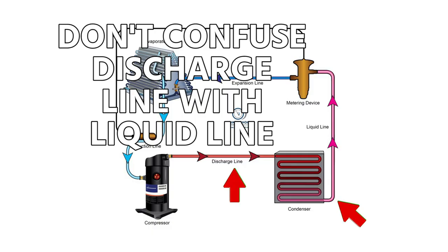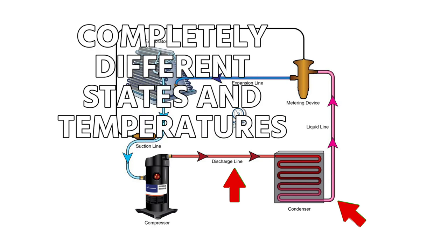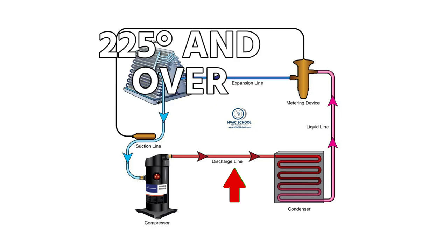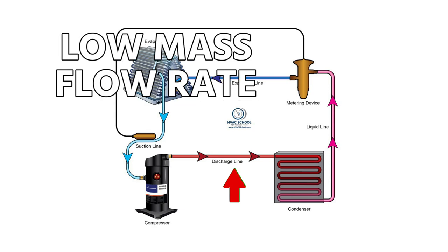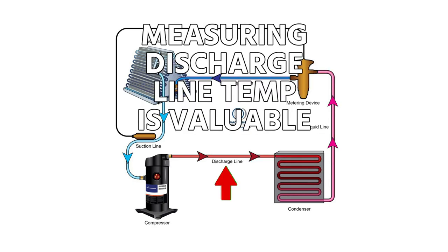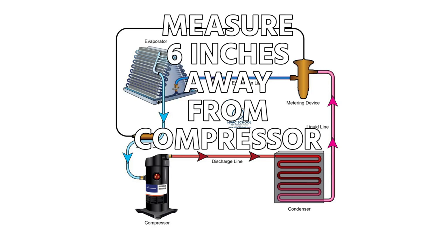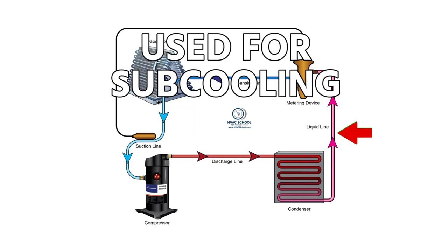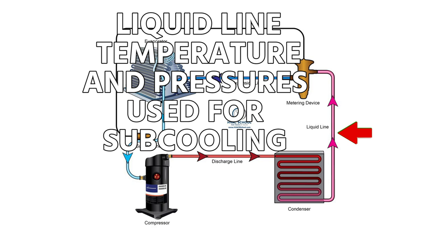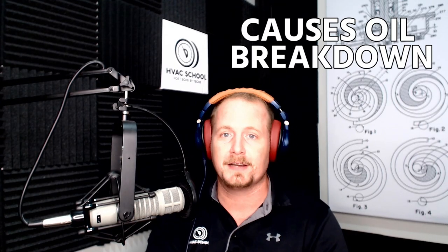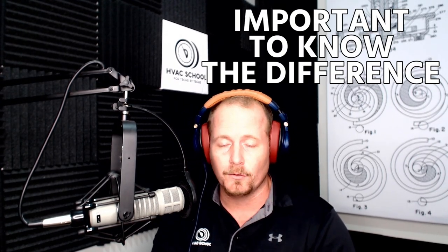Key thing here: don't confuse your discharge line with your liquid line. They're both on the high pressure side, but they are completely different states of refrigerant and temperatures. Discharge line is going to be below 225 degrees. If you ever measure a discharge line temperature of 225 or over, that's an indication of a problem — could be due to low mass flow rate through the compressor, high return temperatures or high superheats. Measuring discharge line temperature is valuable; measure it six inches away from the compressor and make sure it's below 225 degrees. Liquid line temperature and pressure is used for subcooling. Your discharge line temperature helps us see if potentially we have a problem with compressor overheating. It's important to know the difference, and hopefully you found this helpful.